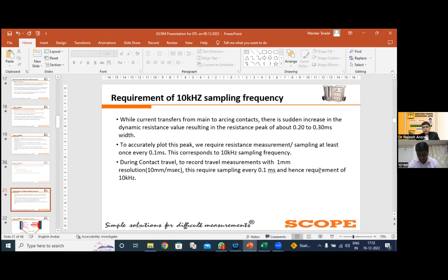An important thing at the time of preparing the setup for the DCRM operation is the requirement of a 10 kilohertz sampling frequency. We need to set the sampling frequency equal to 10 kilohertz. The second important parameter we need to set is delay TCO equal to 300 milliseconds. I have particularly highlighted that at the time of performing the timing operation, your delay TCO should be equal to close time minus 10 milliseconds. In case of DCRM, according to the thumb rule and the duty cycle defined in IEC 62271-100, the duty cycle is 300 milliseconds, so we keep delay TCO equal to 300 milliseconds.